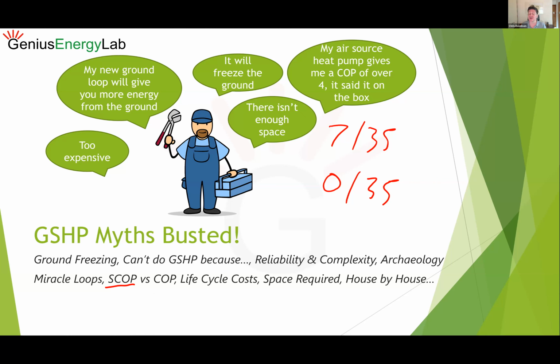To do that, you need to understand not just the air temperature, but the humidity in the air. In the British Isles, we've got unfortunately that climate that never gets very cold, and it's always a bit wet in the winters. So you get defrost cycles happening on air source, frost forming on the coils which needs to be defrosted, and that dramatically reduces the efficiency of the system.